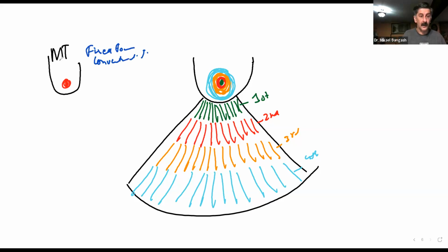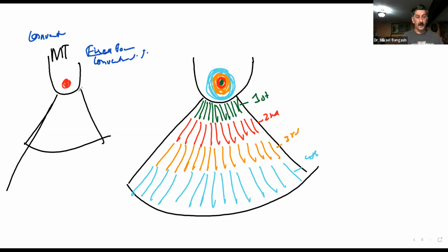So your mechanical transducer could also be referred to as a conventional transducer, which means it has a conventional focusing, which was fixed. So it is only able to focus at one point. Now you may have a greater depth of the image, but the focal point may just be here.